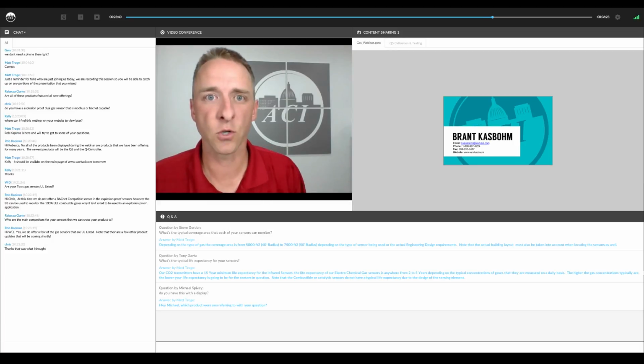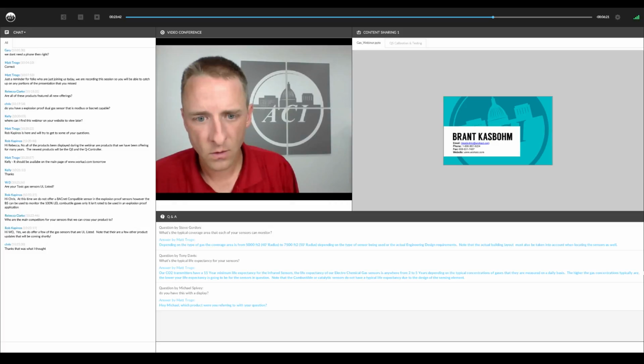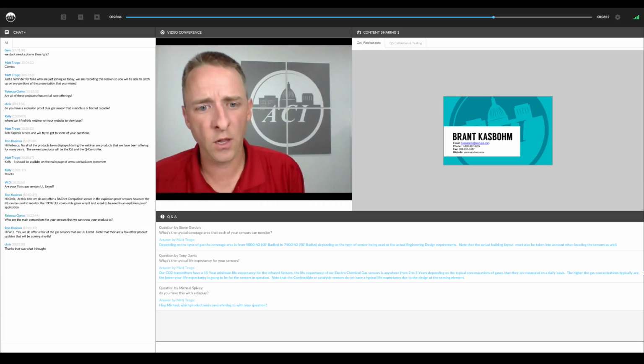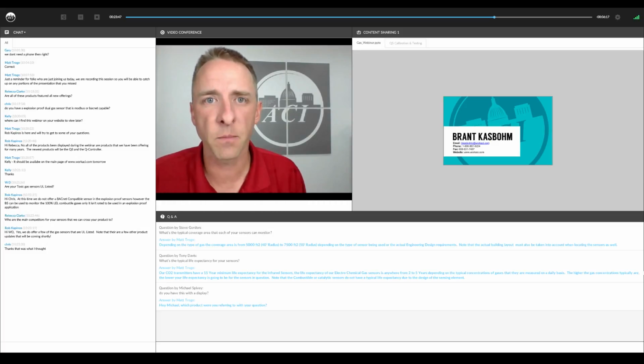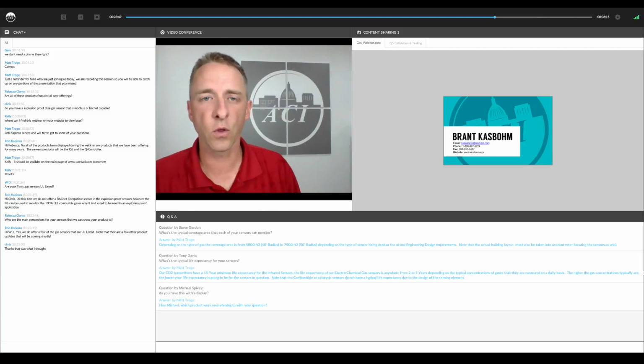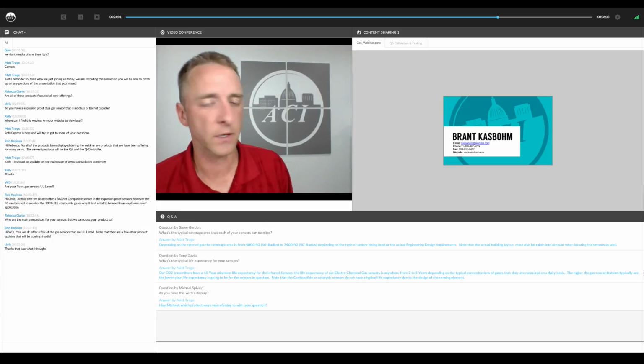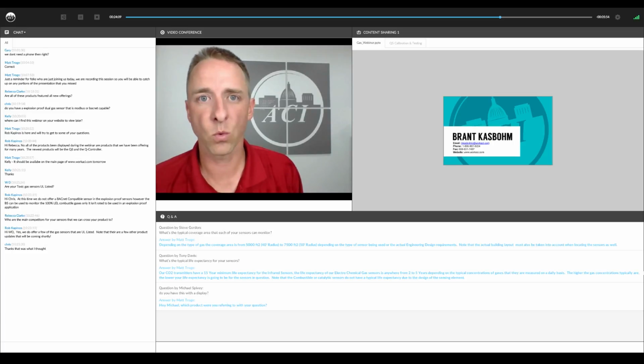The question about CO2 sensor elements being replaceable. I might have mentioned that a minute ago. For CO2 sensors, no, those elements are not replaceable. All of our CO2 sensors are backed by a 5-year warranty, and there's really no need for replacement of a CO2 sensor in the field. Typical life expectancy of our CO2 sensors is 15 years and beyond. And if there's an issue with that, we're certainly happy to work with you on that and replace anything under warranty if a sensor is not behaving properly within a 5-year warranty period.